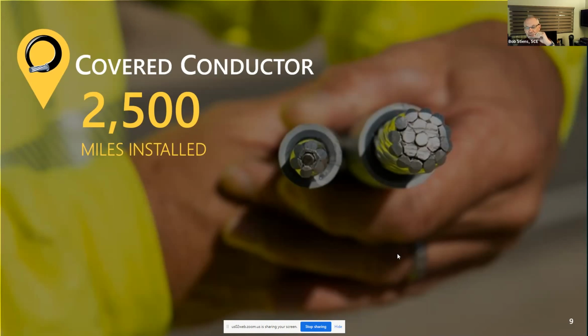This covered conductor doesn't completely eliminate risk, because it still has to connect to the poles, but it's about a 65 to 70% reduction in wildfire risk. In fact, during the Thanksgiving windstorm and PSPS event, we found trees lying on these lines with covered conductor, and the line didn't even relay or start a fire. This is a major part of our wildfire mitigation strategy, along with fuses and switches.